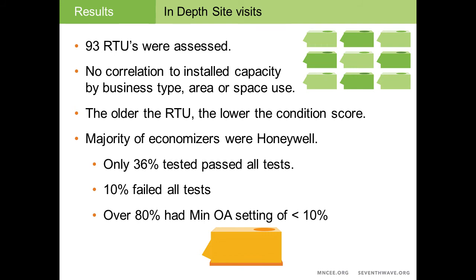Some of the other information that we collected as a result of the in-depth site visit was to document the economizers. And of the economizers that we looked at, Honeywell was predominantly the economizer manufacturer controller that was used. And then as I referenced from the 3 tests that we did before, only 36, or about a third of the units tested, passed all 3 tests that we performed on them, which is an indication of economizers still having some areas that need to be looked at. A smaller subset, only 10%, I should say, failed all the tests. So there is a good indicator out there that economizers are still failing.